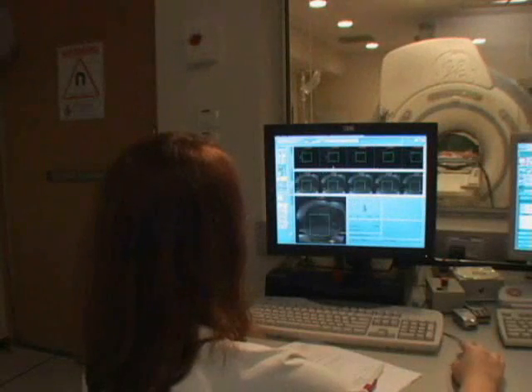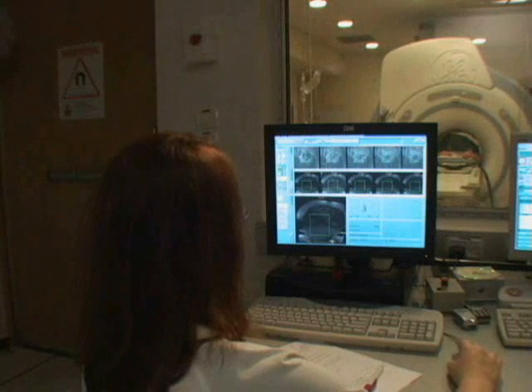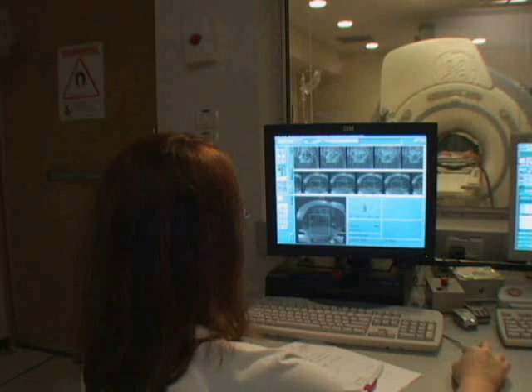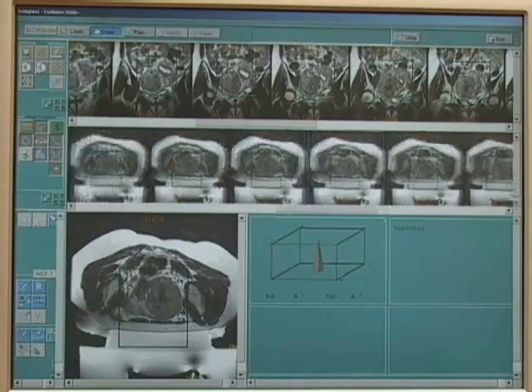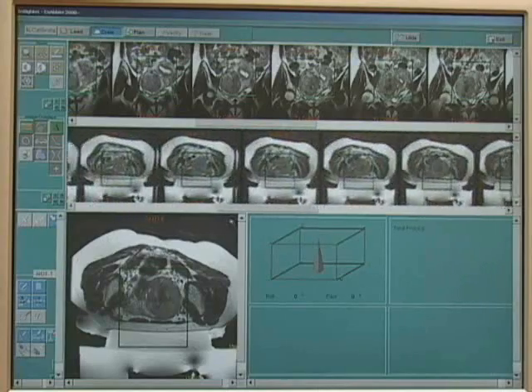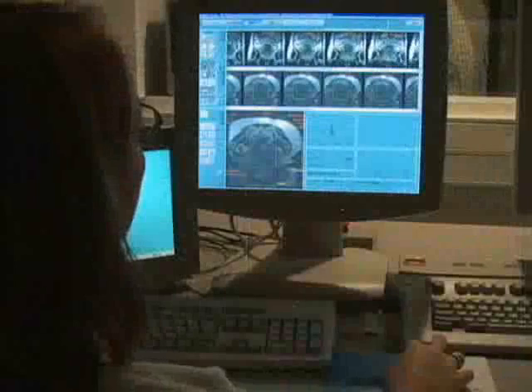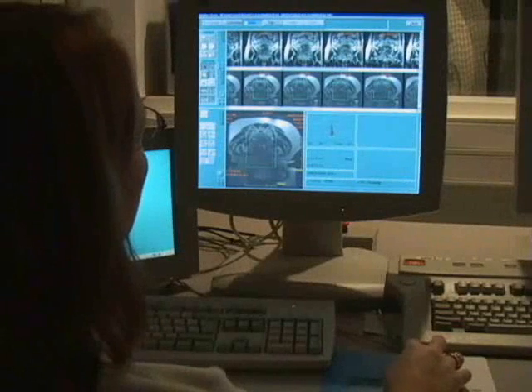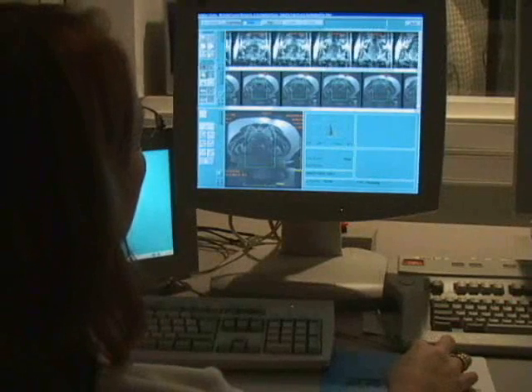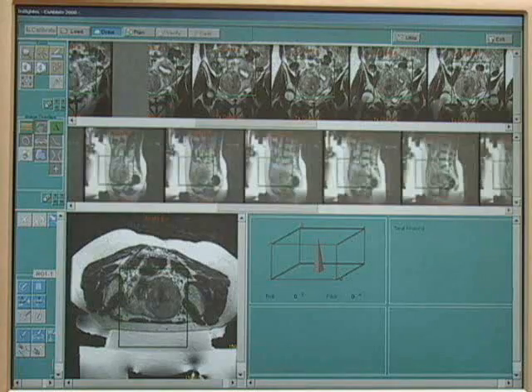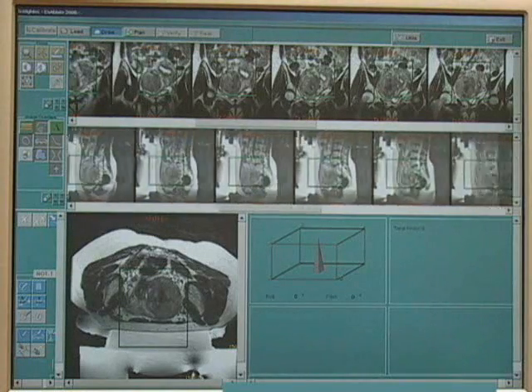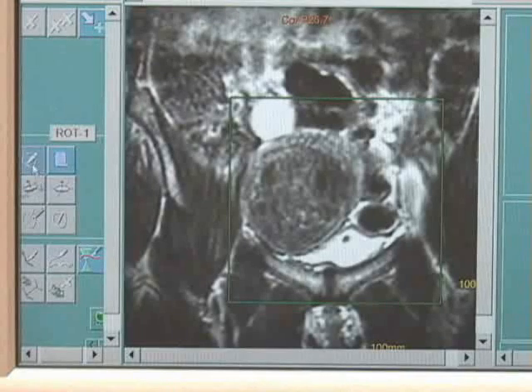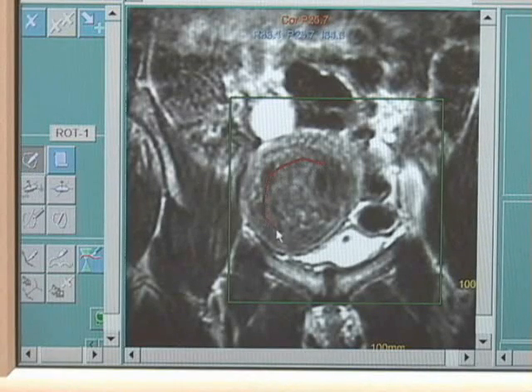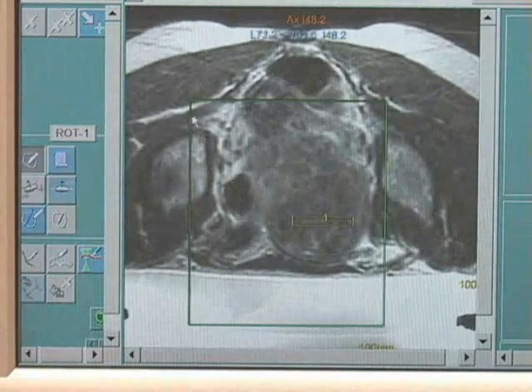Images of the pelvic area are acquired by the MR scanner and retrieved by the Exablate system. From this point on, the Exablate system interfaces with the MRI, and all operations are performed from the Exablate console. Two rows of scans are displayed in strips of images along the top of the workstation screen, displaying slices of two orientations, axial, coronal, or sagittal. The physician selects the treatment area and draws it on the coronal scan. This is confirmed in the other orientations.